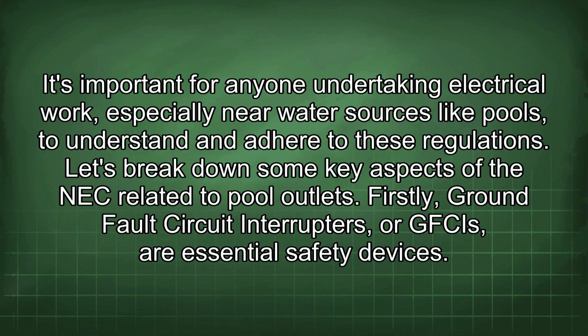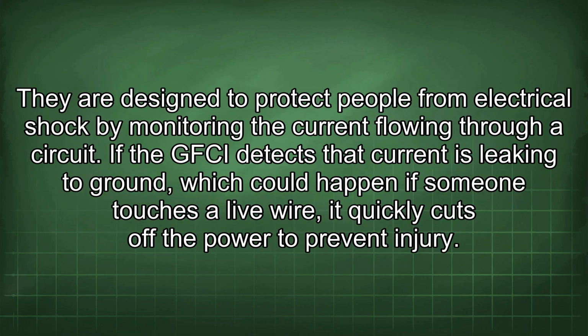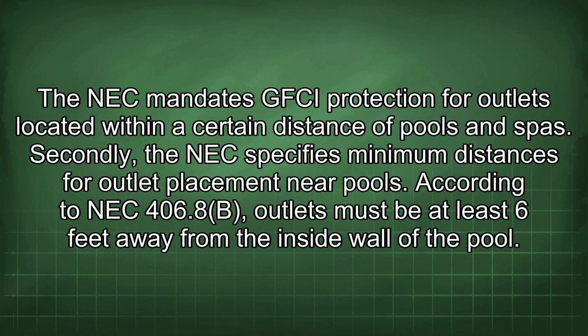Firstly, ground fault circuit interrupters, or GFCIs, are essential safety devices. They are designed to protect people from electrical shock by monitoring the current flowing through a circuit. If the GFCI detects that current is leaking to ground, which could happen if someone touches a live wire, it quickly cuts off the power to prevent injury. The NEC mandates GFCI protection for outlets located within a certain distance of pools and spas.